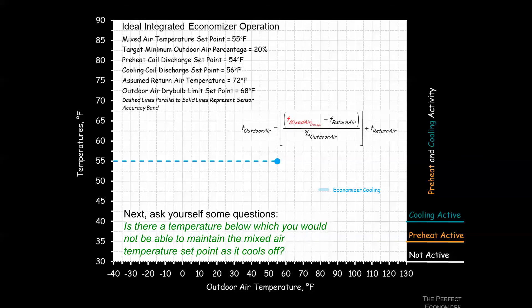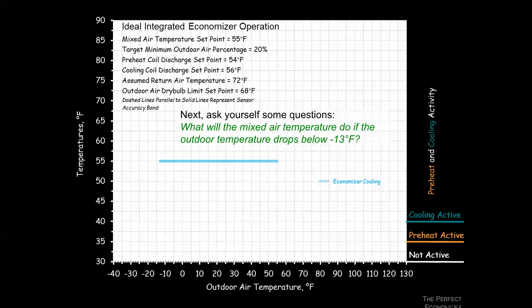Rearranging our equation with 20% outside air, the given return air, and our mixed air set point, we find that at negative 13 degrees we can no longer hit that 55-degree set point. This is a powerful concept — it has to get below negative 13 degrees outside for this system to be unable to meet its mixed air temperature. Below that, at negative 40 degrees, we'd see approximately 50 degrees mixed air, assuming ideal mixing.